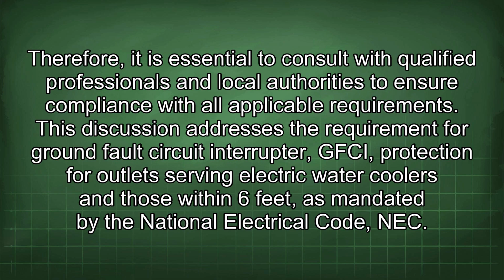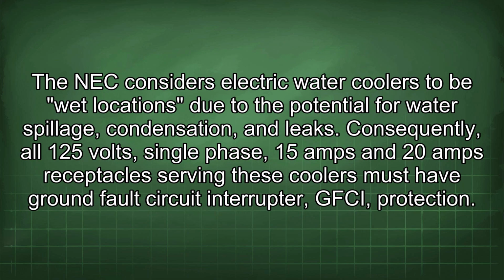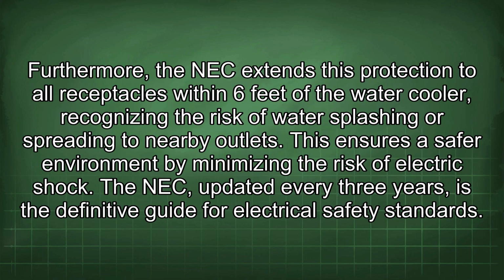This discussion addresses the requirement for ground fault circuit interrupter (GFCI) protection for outlets serving electric water coolers and those within 6 feet, as mandated by the National Electrical Code (NEC). The NEC considers electric water coolers to be wet locations due to the potential for water spillage, condensation, and leaks. Consequently, all 125 volts single-phase, 15 amps and 20 amps receptacles serving these coolers must have ground fault circuit interrupter (GFCI) protection. Furthermore, the NEC extends this protection to all receptacles within 6 feet of the water cooler, recognizing the risk of water splashing or spreading to nearby outlets. This ensures a safer environment by minimizing the risk of electric shock.